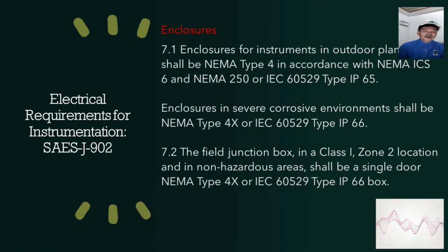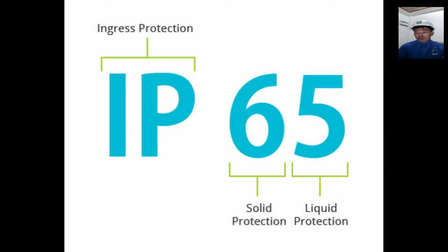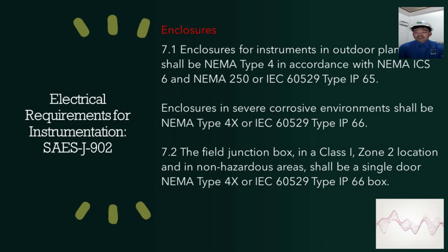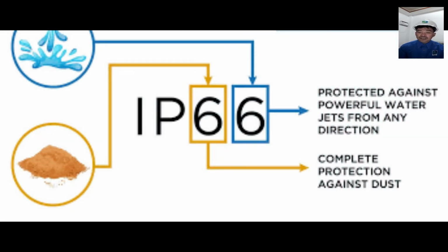We have enclosure material specification requirements for all the areas. Enclosures for instruments in outdoor plant areas shall be NEMA Type 4 in accordance with NEMA ICS 6 and NEMA 250, or IEC 60529 Type IP65. So these are the requirements for the outdoor plant areas. Enclosures in severe corrosive environments shall be NEMA Type 4X or IEC 60529 Type IP66. So this is a much higher rating compared to the first one, because this is a severe corrosive environment. NEMA Type 4X is stainless steel.